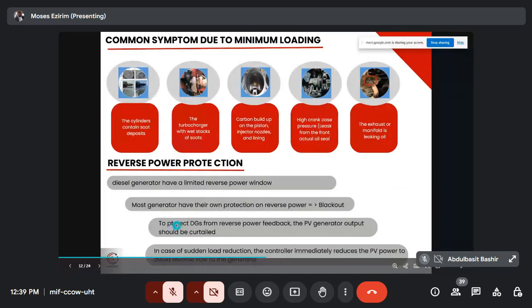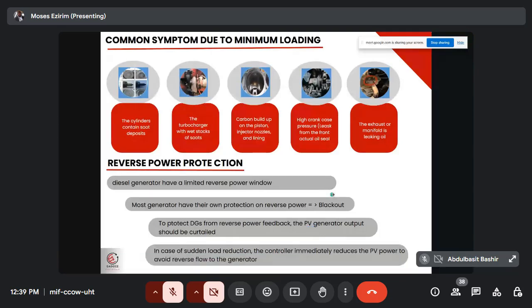Now, to protect the generator from reverse power, curtailment is used. What is the meaning of curtailment? You are going to see it as we proceed. Now, in case of a sudden load reduction, the controller immediately reduces the flow. The controller is very, very smart, so it knows what to do as far as you've done the settings. So this is for reverse power.